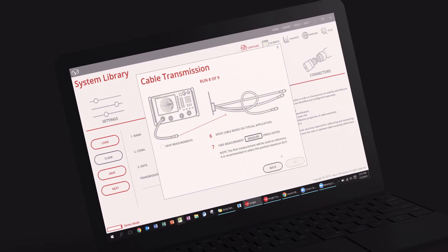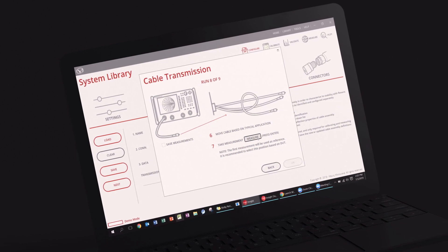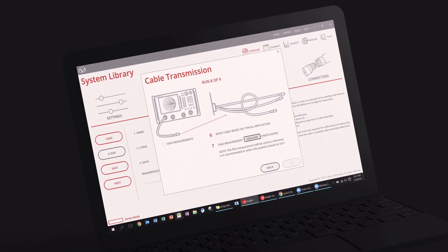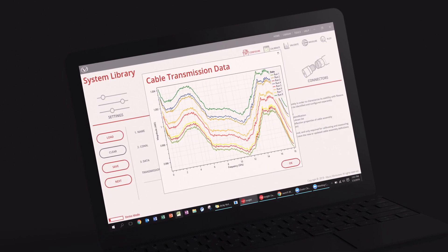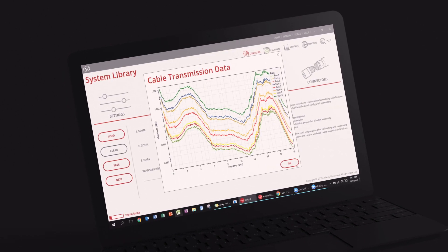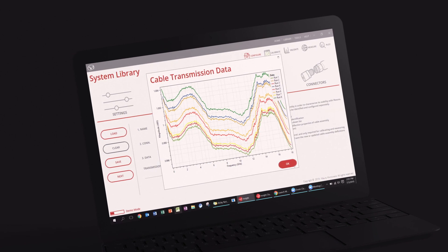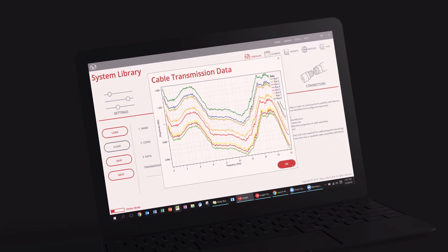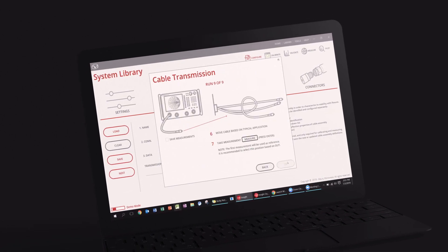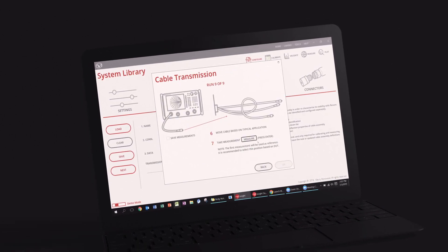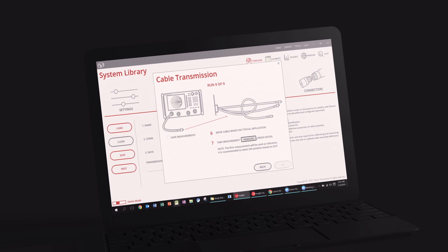This is done in the same manner that a user would bend the cable during their measurements, ensuring that the uncertainty is quantified for the specific movements associated with each user's test and not a generalized or ideal bend. This test does not rely on any data or information provided by the cable vendor.